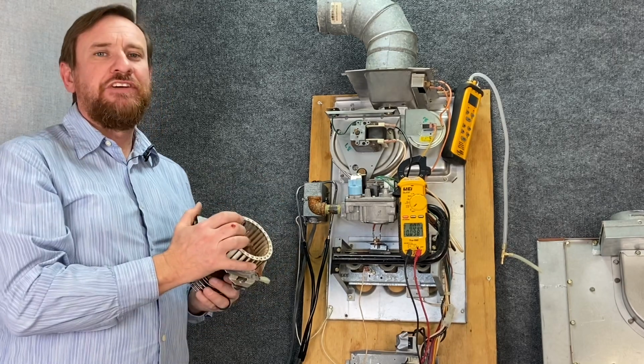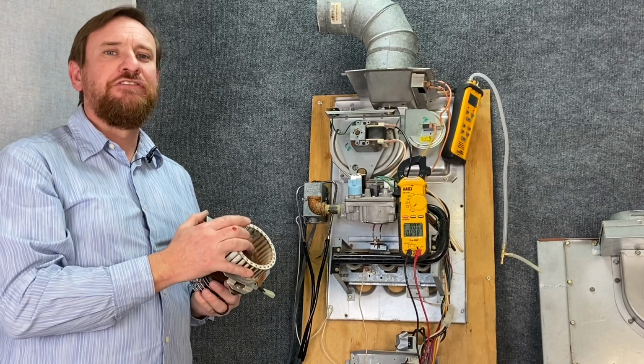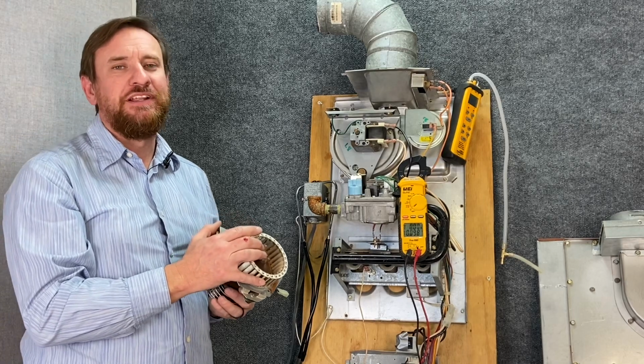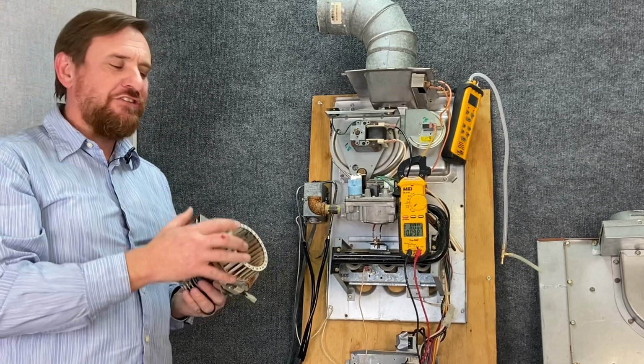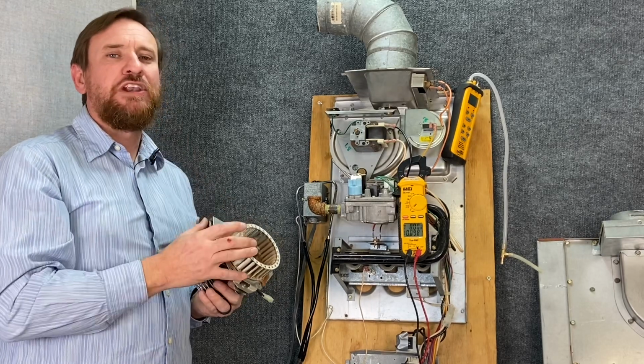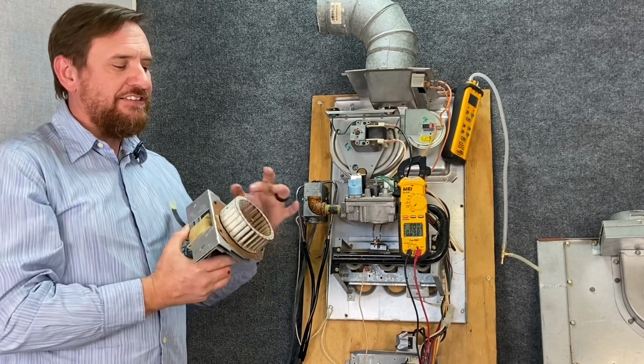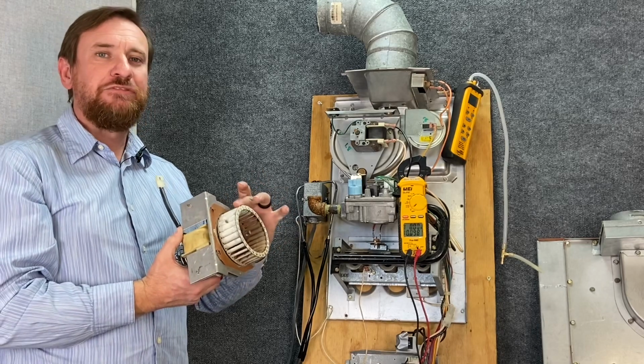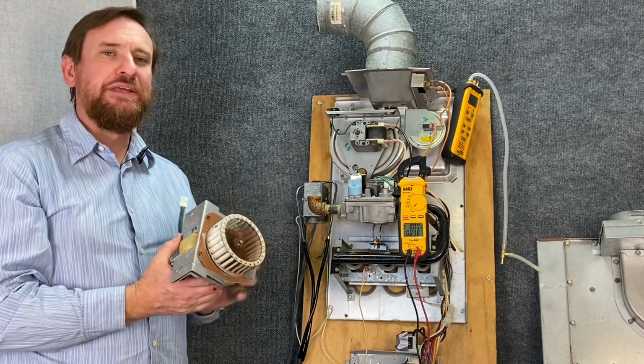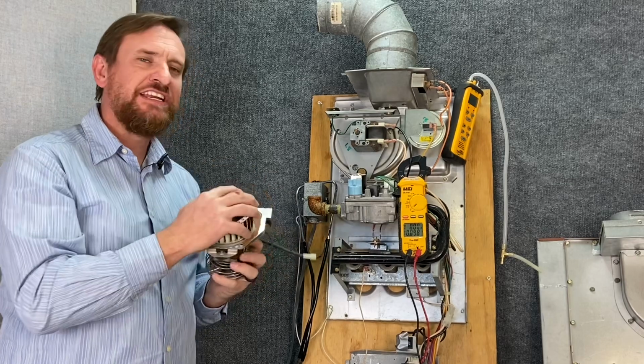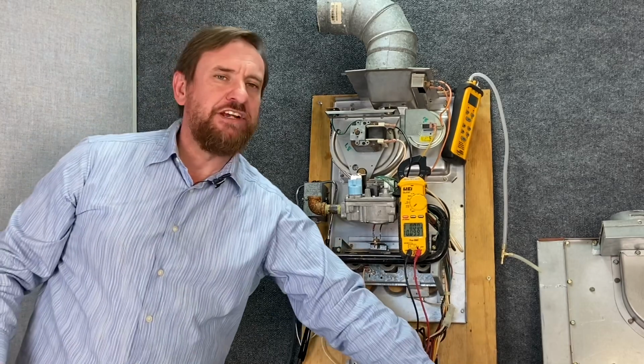These are type 1 furnaces, so we need to make sure that our flue gas temperature is above dew point. If we draft it too fast, we'll actually take away too much heat and that water will condensate. That condensation is horrible, and if we see that on this motor, it's a red flag that we have a big issue going on. So seeing the condition of this wheel is very important.